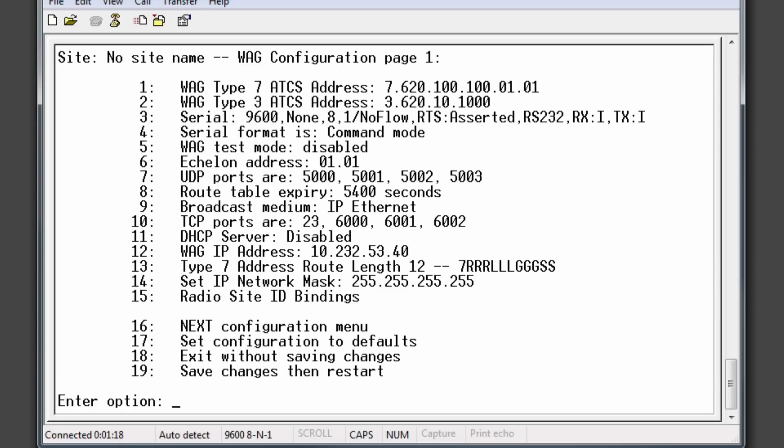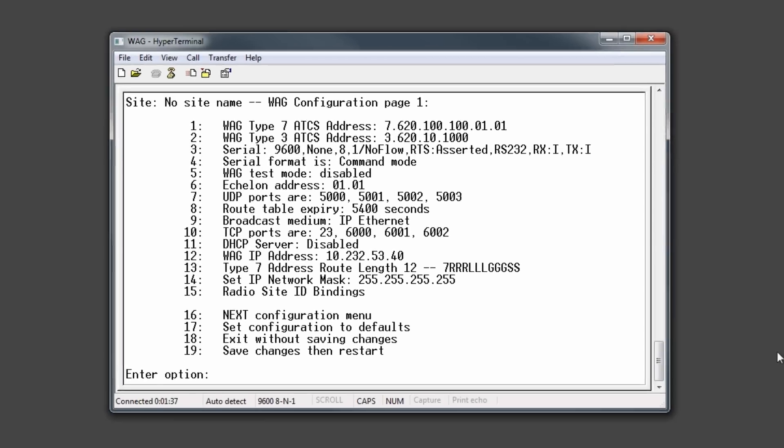The type 3 ATCS address is typically the same for all WAG units across your system. For the echelon address, the last two digits indicate the echelon slot on the SEARS III that the WAG has been assigned to. For example, if the WAG has been assigned to slot 3 on the SEARS III, the WAG echelon address should be 01.03.